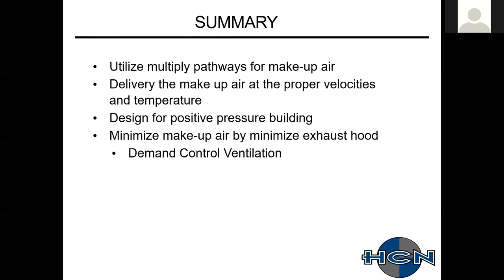Next thing I would say is proper air velocities is probably the next biggest thing. If your air velocities are too great near the hood, you're going to be pulling effluent smoke and grease out, and it's just going to cause problems for the rest of the HVAC system as well as the cooking staff in the space. You're going to increase the temperatures. It's going to be a little bit more humid. You're putting extra work on that rooftop unit.